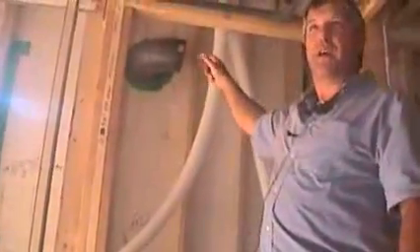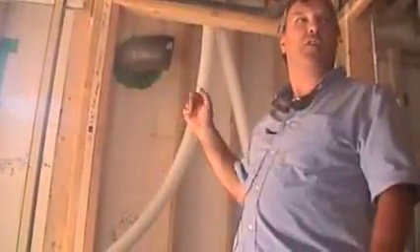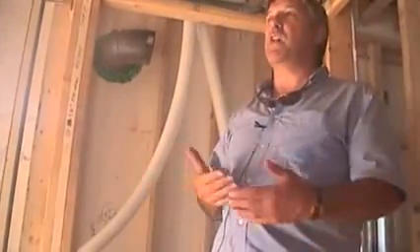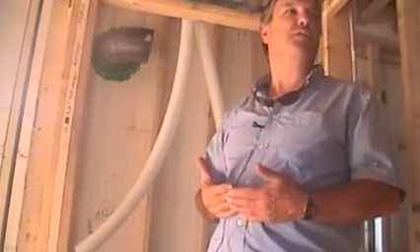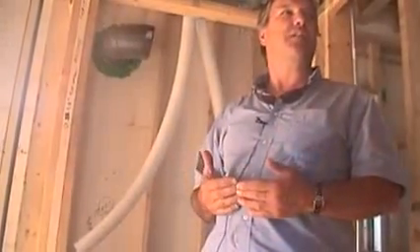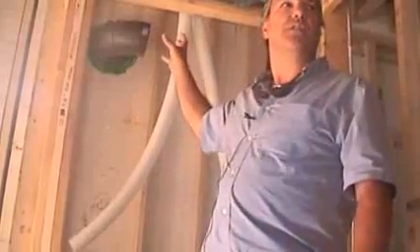Keep in mind that the air coming in, if it's 30 degrees outside, is coming in at 30 degrees. The air that's going out is about 32. Because the heat recovery ventilator is over 90% recovery efficiency, the air that's leaving that unit is pretty close to what's outside. So both of those ducts have to be insulated to the outside.